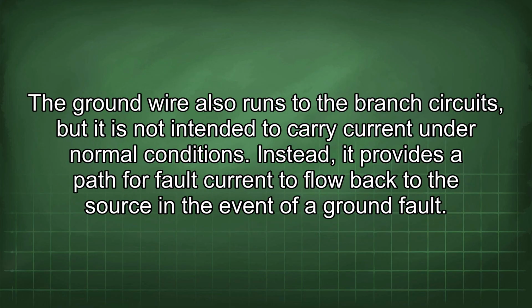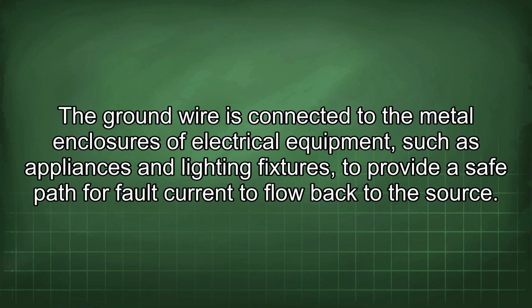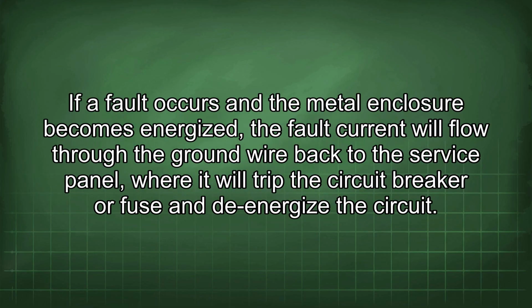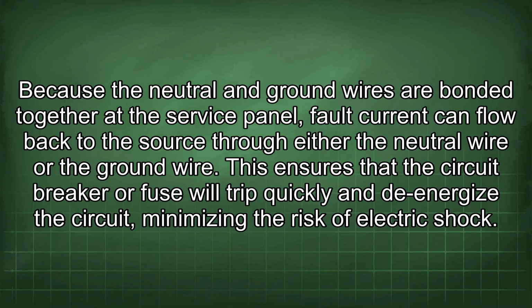The ground wire also runs to the branch circuits, but it is not intended to carry current under normal conditions. Instead, it provides a path for fault current to flow back to the source in the event of a ground fault. The ground wire is connected to the metal enclosures of electrical equipment, such as appliances and lighting fixtures, to provide a safe path for fault current to flow back to the source. If a fault occurs and the metal enclosure becomes energized, the fault current will flow through the ground wire back to the service panel, where it will trip the circuit breaker or fuse and de-energize the circuit. Because the neutral and ground wires are bonded together at the service panel, fault current can flow back to the source through either the neutral wire or the ground wire. This ensures that the circuit breaker or fuse will trip quickly and de-energize the circuit, minimizing the risk of electric shock.